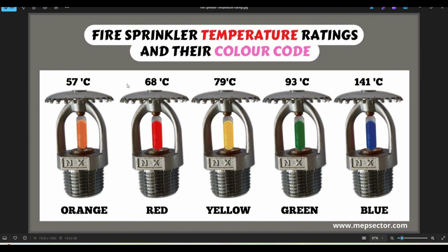Now, based on the application, we use different kinds of temperature ratings. For high hazards, we use the high temperature ones, and for low temperatures we normally use the 68 and 79. The 57, we normally don't use it; in very light conditions the application is there, but normally we use the 68 and 79. If the room is an air-conditioned space, then we will use the 68, and if the air-conditioned space is not there, then you will use the 79.